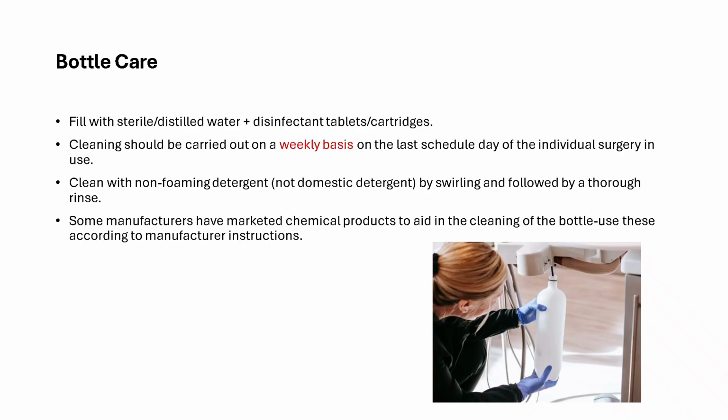Also, make sure that you fill the water used for patients with sterile or distilled water and not tap water, and you can add the biocide as mentioned in the previous slide. The reason why distilled water is used is because it has less minerals and also because it's formed by heating and condensation, so it has less microorganisms.